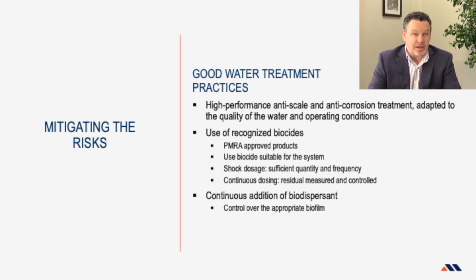Use the approved biocides. So in Canada specifically, we have to have a biocide that's been approved with PMRA, pesticides management regulations, and that has to be done properly with the right conditions, which include contact time, pH, temperature, metallurgy. So those are really important things to do. And always use a biodispersant. It helps keep surfaces clean. It takes away the places where bacteria can hide. And those are three basic ways to manage, at the basic level, Legionella.